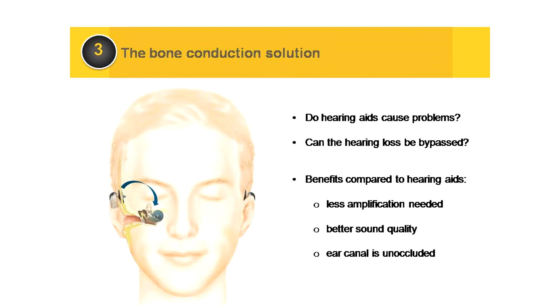This is Cochlear's Baha 5 system in situ, and as you can see, there are 2 options in terms of how the sound is transmitted from the external sound processor to the internal implant. On the left, you'll see the transcutaneous Baha Attract system, which has a magnetic connection across the skin and soft tissue. And on the right, you can see the Baha Connect system, which has a snap-on abutment connection. They both work essentially in the same way. The internal parts are surgically implanted during a fairly short surgery, which takes about 20 to 30 minutes. It's done as a day case. In some places it's done routinely under local anaesthetic, other places routinely under general.